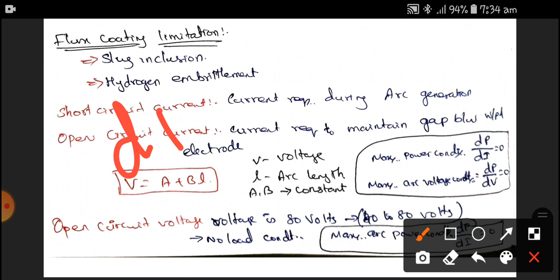For the open circuit voltage, the voltage required is only 80 volts. That is, 40 to 80 volts is enough for the open circuit voltage, and this is for the no load condition. The maximum power condition can be said to be dP/dI = 0. So these conditions are called the drooping characteristics.